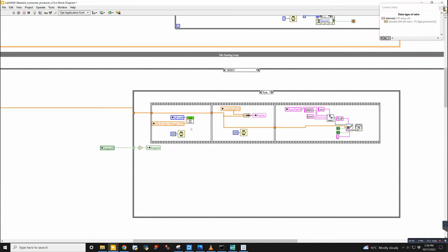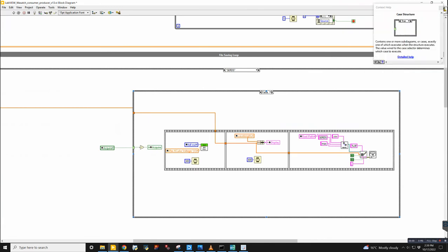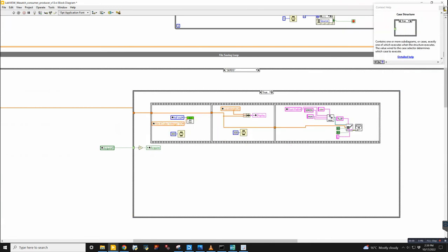So does this actually work? Yeah. It does. Because you're taking a spectrum that's taken before you change the voltage setting, right? Yeah, I see that right now. And then it puts that in here. It will save 2 spectra every time, but if it's the right 2 spectra is the thing. I see. So the first step that needs to happen is you need to go to the minimum K cube voltage, and then you take a spectrum, and then you change the voltage, and then you take another spectrum. So that needs to be the order with that. So I think that needs to be modified.